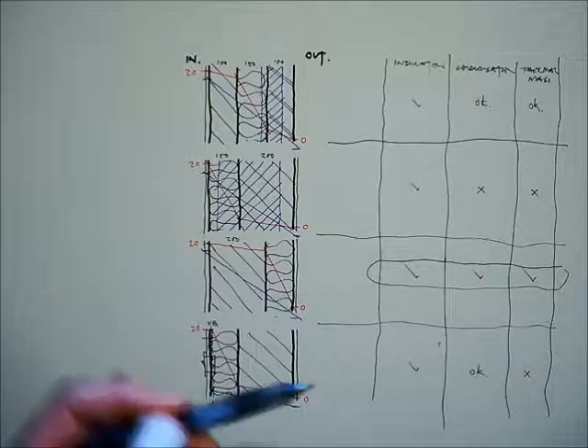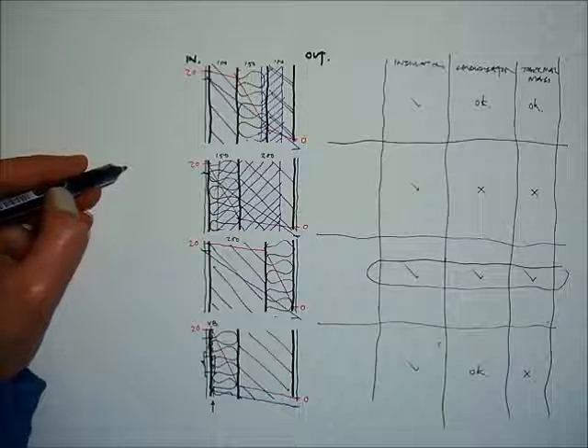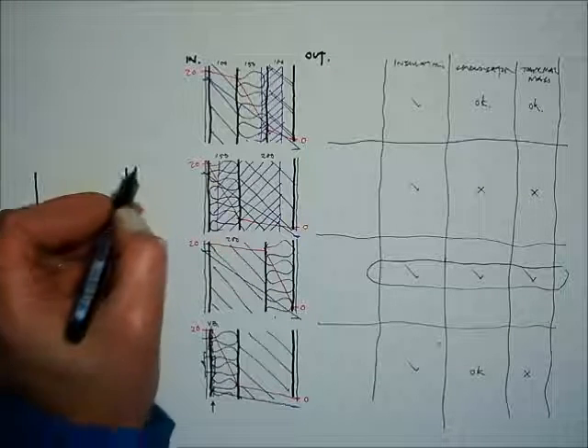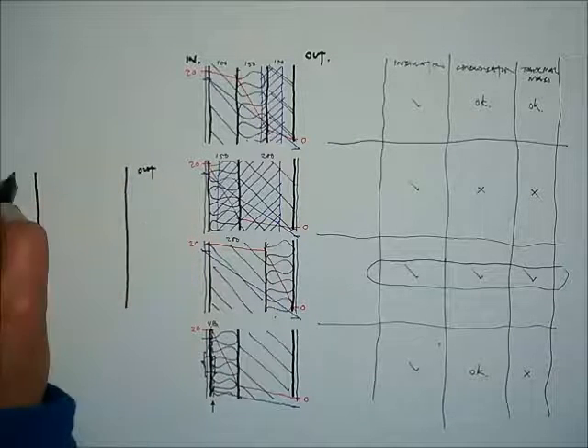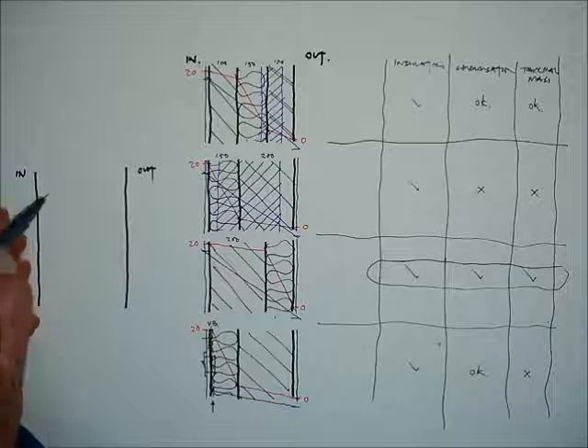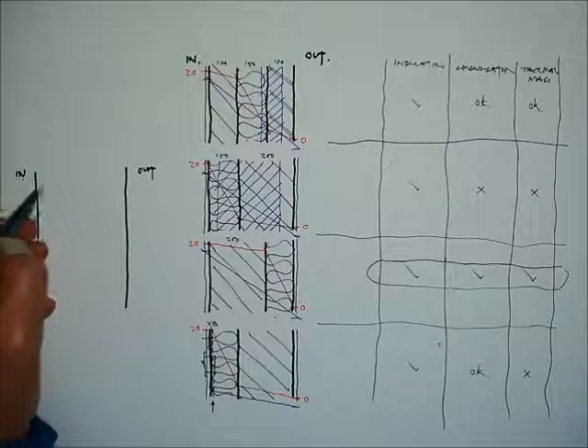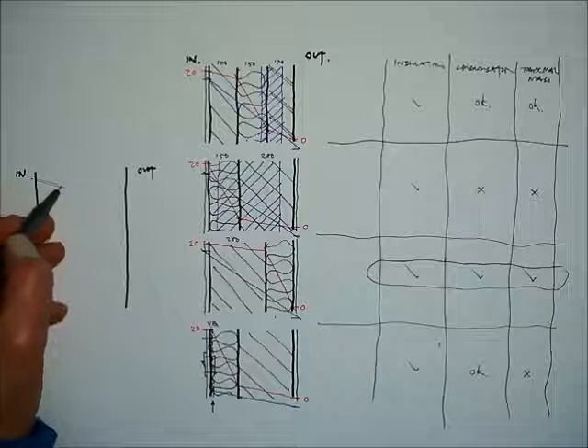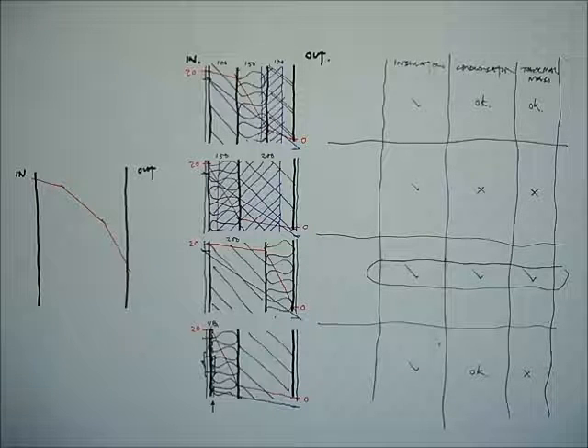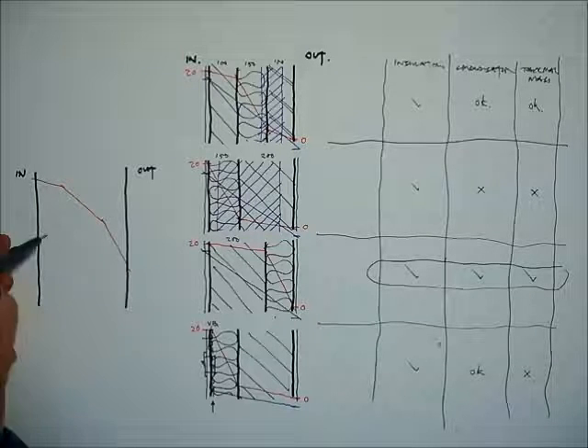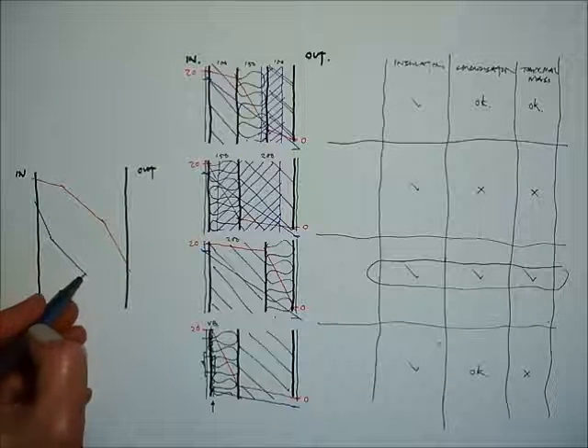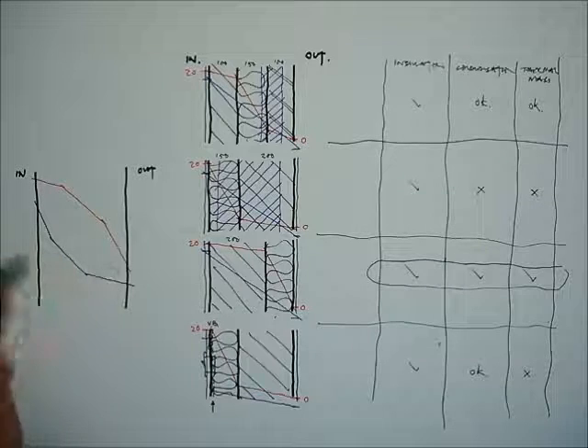So from that diagram, here's some rules of thumb. Here's some wall construction, outside, inside. We want the layers of the construction to force the temperature gradient in this direction and for the layers of construction to force the dew point temperature in this direction away from each other.